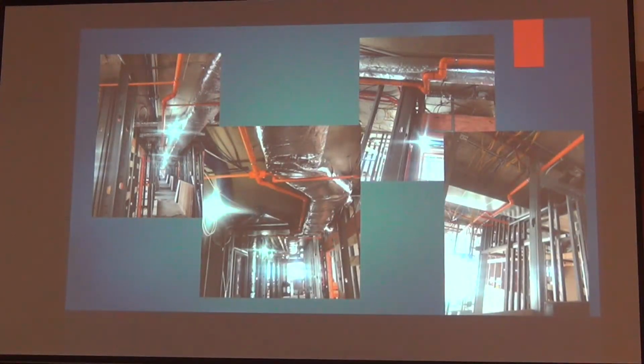All right, this one I throw in here because when you get a set plan, the piping is designed for the flow of the system. And as we all know, 90 adds 15 feet of pipe for friction. This plan, when it was submitted, the sprinkler line was going straight down the hallway. I think it was 102 feet of run. Doesn't sound like much, but it was a big hotel. Anyway, they were late to the party, so they had to work around everybody.